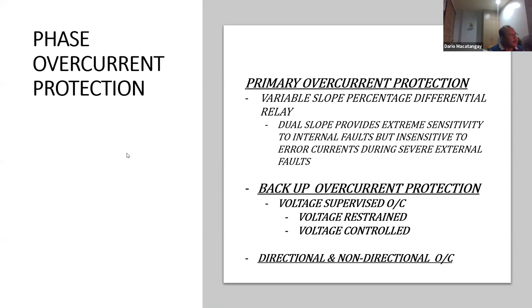Okay. Now, backup overcurrent protection. It is a little bit difficult to set the backup overcurrent protection because of the presence of that Xd that I told you about a while ago, because of the changing characteristic of the impedance of the generator. When you have a fault, that impedance is very small, leading to high current, okay? And as the fault progresses, it decays exponentially. So the impedance now becomes bigger, and the current becomes smaller.